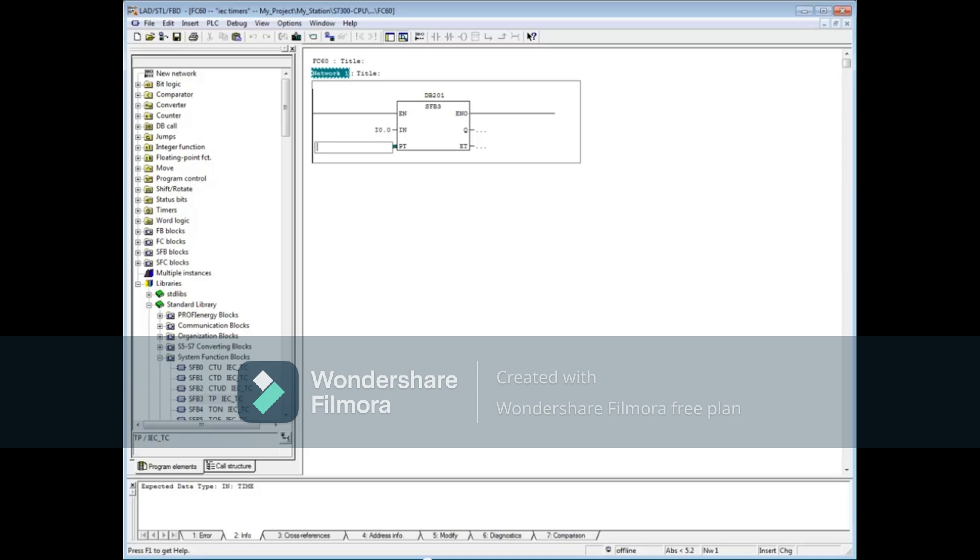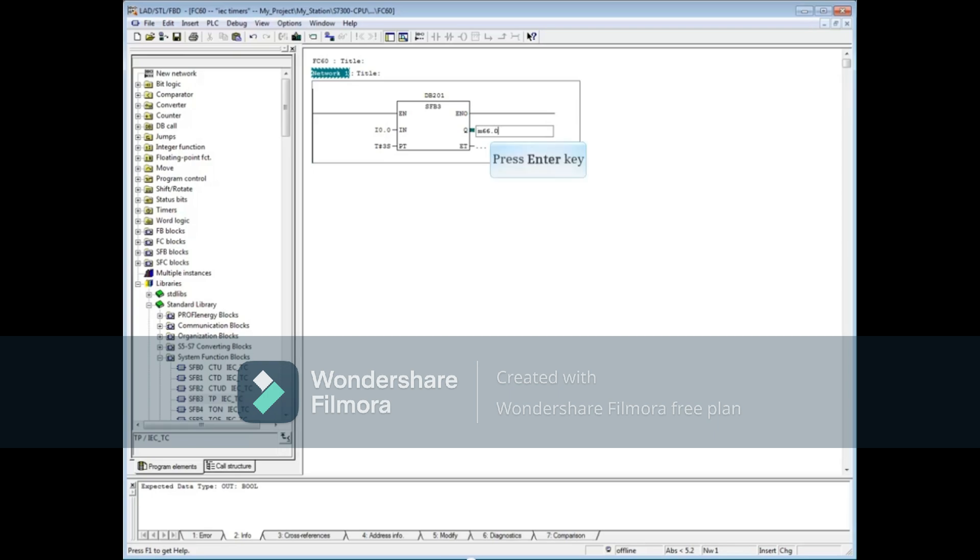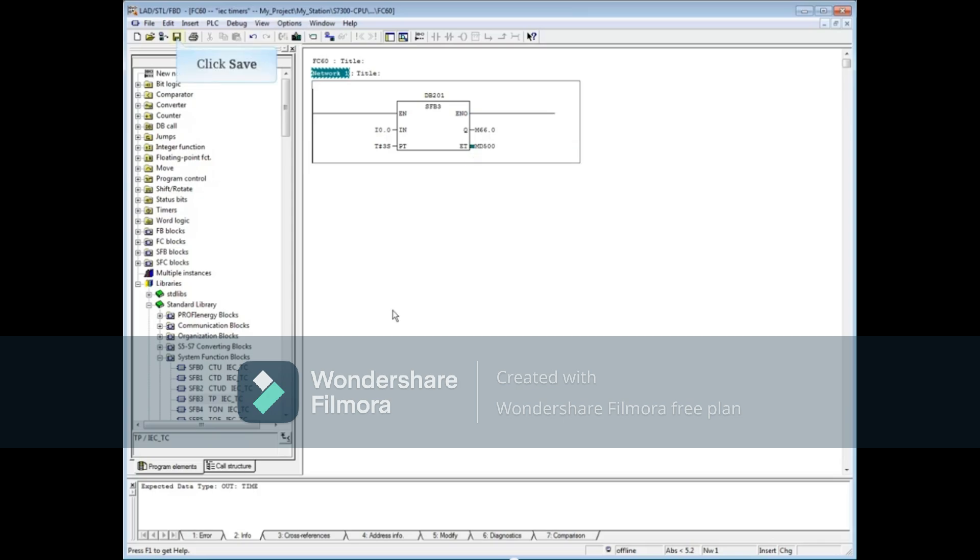We will make this timer's value T-pound three seconds and press the Enter key. Let's set the output to energize memory bit 66.0 and press the Enter key. Let's store the elapsed time value in memory double word 500. Save the block.